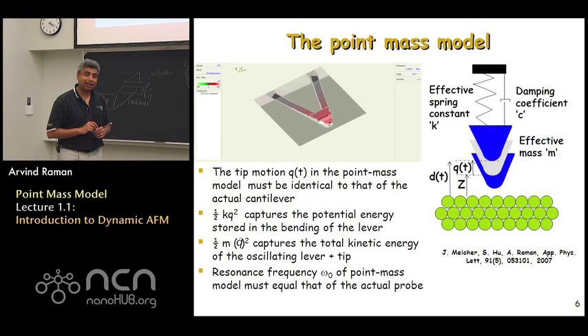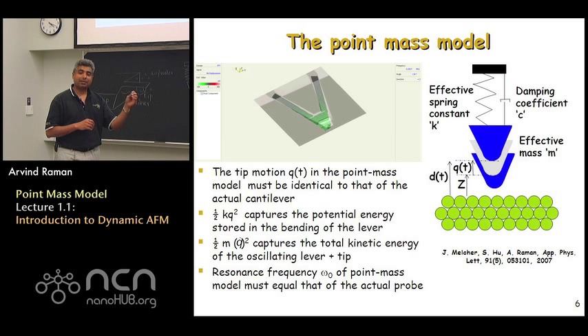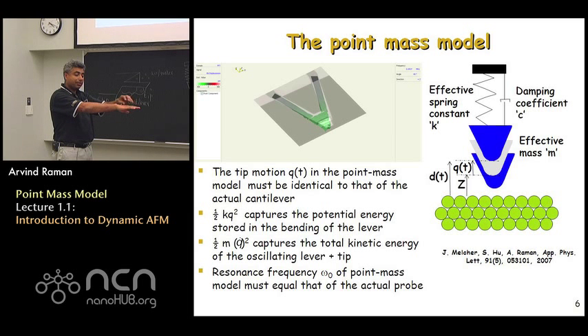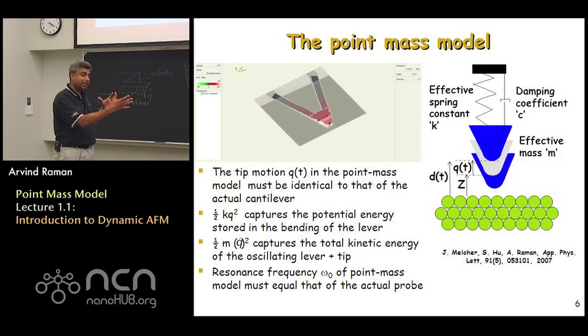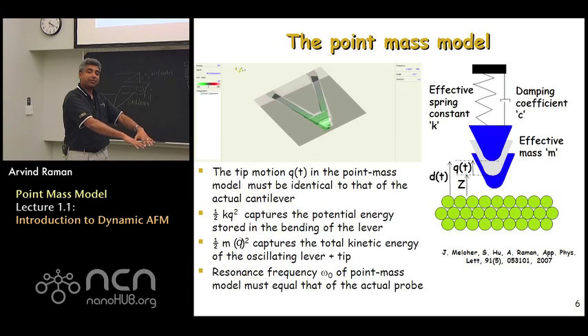That equivalence of potential energy determines the effective spring constant k. A second important equivalence is kinetic energy: one-half m q-dot-squared for the point mass model must equal the kinetic energy of the actual probe. The actual probe's kinetic energy includes both the tip mass moving up and down and the distributed mass along the cantilever arms. Therefore, the effective mass m of the point mass model is not simply the mass of the AFM tip, but a measure of the overall probe mass.